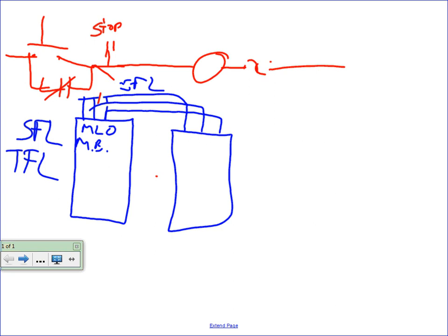Through feed lugs is where we actually put the lugs on the opposite side of the panel. So it actually feeds through the panel and comes out the opposite direction. Where we use this a lot is at high rises, right? Where you got electrical rooms stacked up on top of each other, each floor. They'll come in the bottom of the panel and out the top to feed the next panel. You just keep going. So that's feed through because we're feeding through that panel, the lugs are on the opposite side. Sub-feed, the lugs are on the same side.